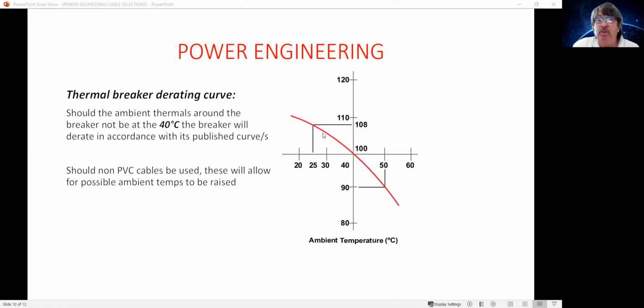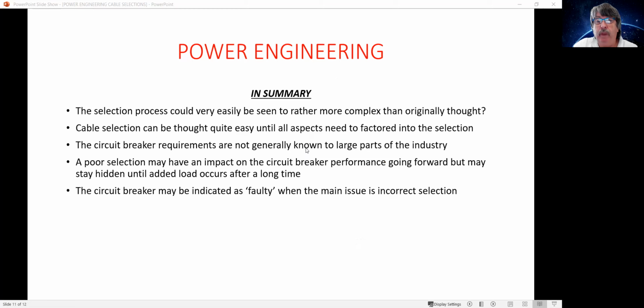This leads us to another point where we should very, very carefully suggest that if a circuit breaker is sitting in a very warm panel board, and it feeds to a very cold load area, in other words, the cable goes out in a much lower temperature, the performance is different to where it's actually being seen, because the performance will be measured by that circuit breaker in its local environment. So it's very important where you have a hot panel board and a cold load area, or the other way around, a cold panel board area and a very hot load area where the cable is under stress from additional temperatures around it. So it will not have optimal protection from the cable, which is in a cold state, which will then take longer to trip. So that's kind of where we're going to have a look at today.